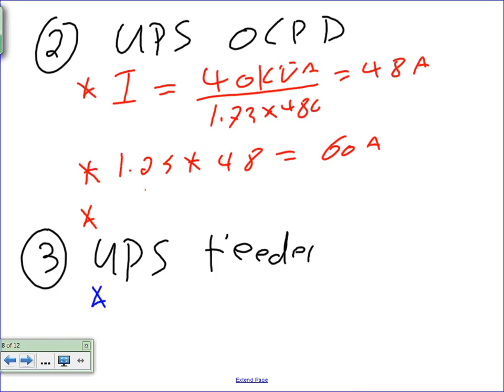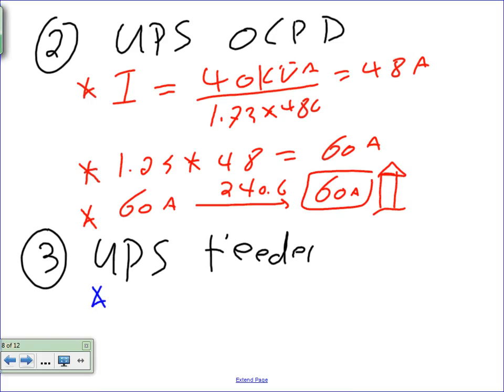And that will give me 60 amps. And if you take the 60 amps, take it to 240.6. If it's not a standard, go up, but it's actually 60 amp is a standard. That's it. So I have a 60 amp overcurrent device on the primary side of the UPS. Cool? UPS feeder, guys, is the same thing. 1.25, multiply it by 48, same, almost match the overcurrent device, equals 60 amp.